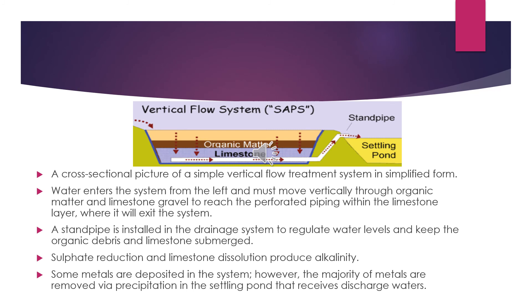Here we're going to look at the vertical flow system, also known as SAPS. There is a cross-sectional picture of a simplified vertical flow treatment system. Water enters the system from the left and must move vertically through organic matter and limestone gravel to reach the perforated pipe within the limestone layer, where it exits the system. A standpipe is installed in the drainage system to regulate water levels and keep the organic debris and limestone submerged. Sulfate reduction and limestone dissolution produce alkalinity. Some metals are deposited in the system; however, the majority of metals are removed via precipitation in the settling pond that receives discharge waters.